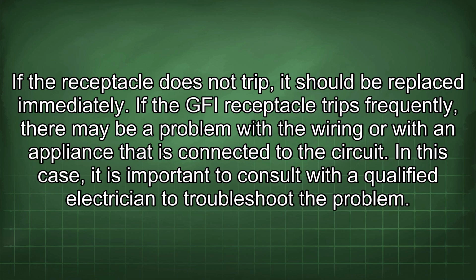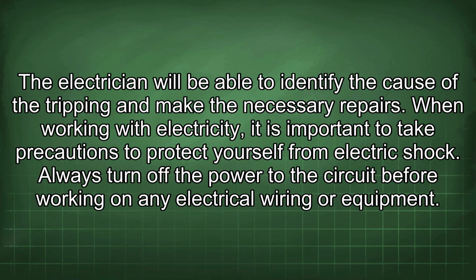If the GFI receptacle trips frequently, there may be a problem with the wiring or with an appliance that is connected to the circuit. In this case, it is important to consult with a qualified electrician to troubleshoot the problem. The electrician will be able to identify the cause of the tripping and make the necessary repairs.